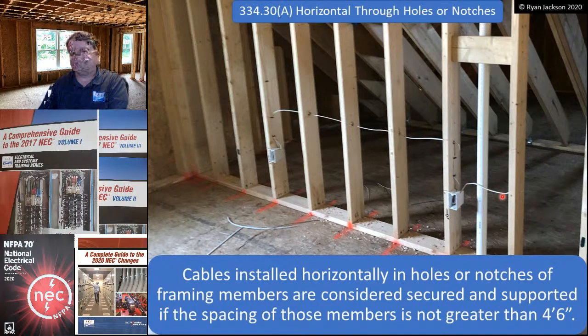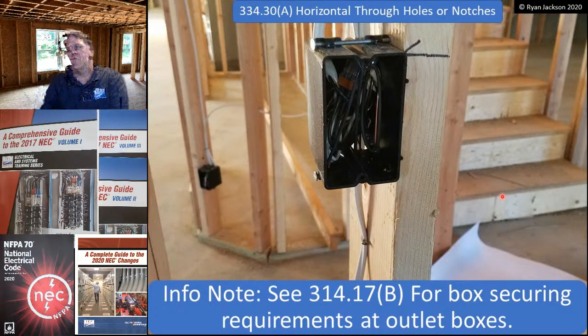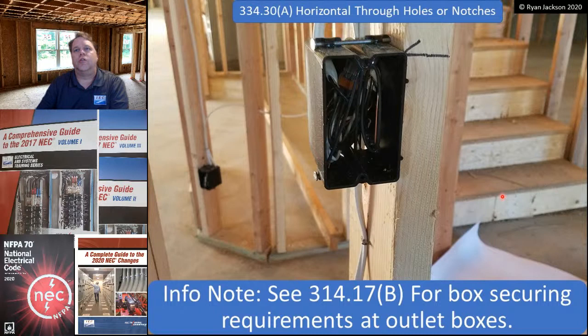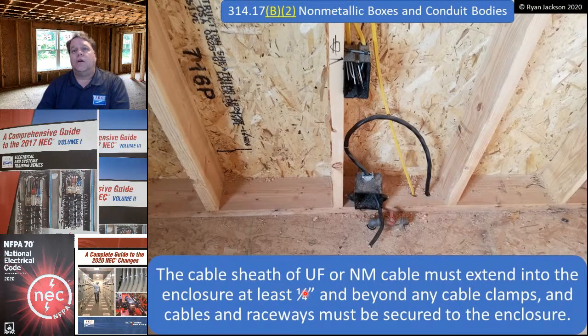There's also an informational note in this section, and I think it's a good one, that says, hey man, while you're here, look at 314.17(B) for box securing requirements at outlet boxes, I should say cable securing requirements. What that section says is the cable sheath of UF or NM cable must extend into the enclosure at least 1/4 inch beyond any cable clamps, and cables and raceways must be secured to the enclosure. So you have to secure the cable to the box.